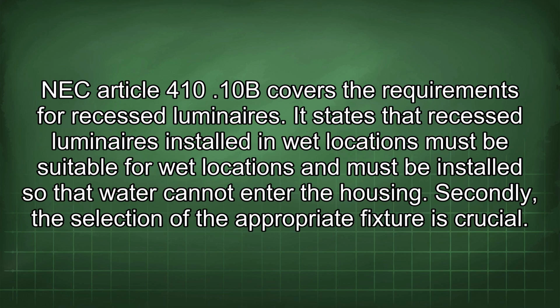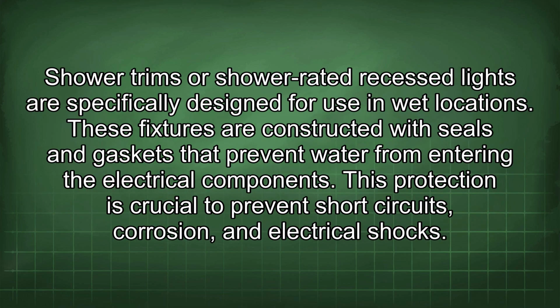NEC Article 410.10(B) covers the requirements for recessed luminaires. It states that recessed luminaires installed in wet locations must be suitable for wet locations and must be installed so that water cannot enter the housing. Secondly, the selection of the appropriate fixture is crucial. Shower trims or shower-rated recessed lights are specifically designed for use in wet locations.